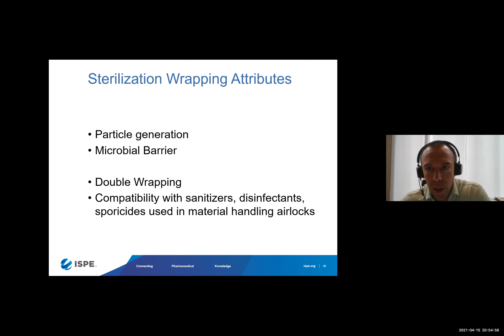So from a sterility assurance standpoint, the microbial barrier needs to be compared between paper and polyolefin. Particle generation needs to be compared. The idea of double wrapping and compatibility with sanitizers, disinfectants, and sporicides. So I would say from a sterility assurance standpoint, these are the attributes that are most compelling when comparing paper and polyolefin.